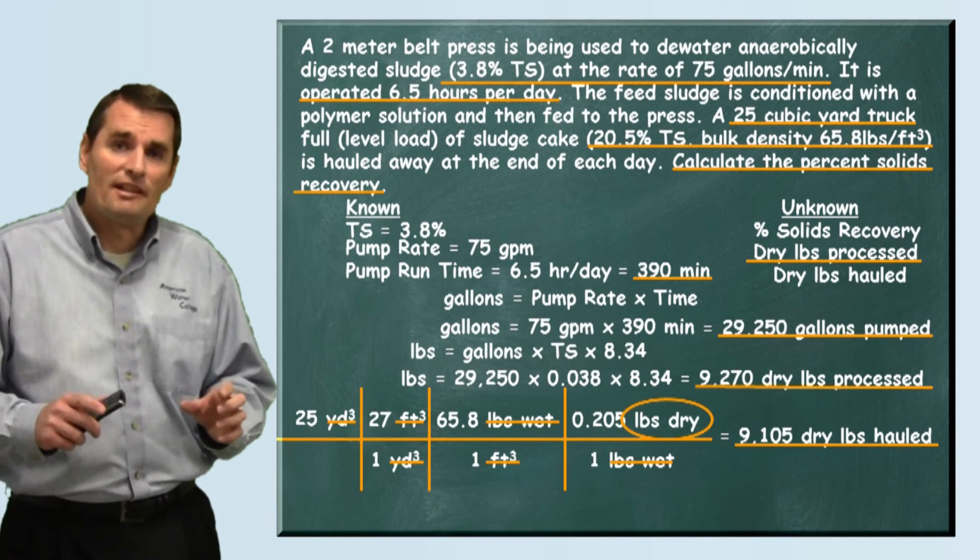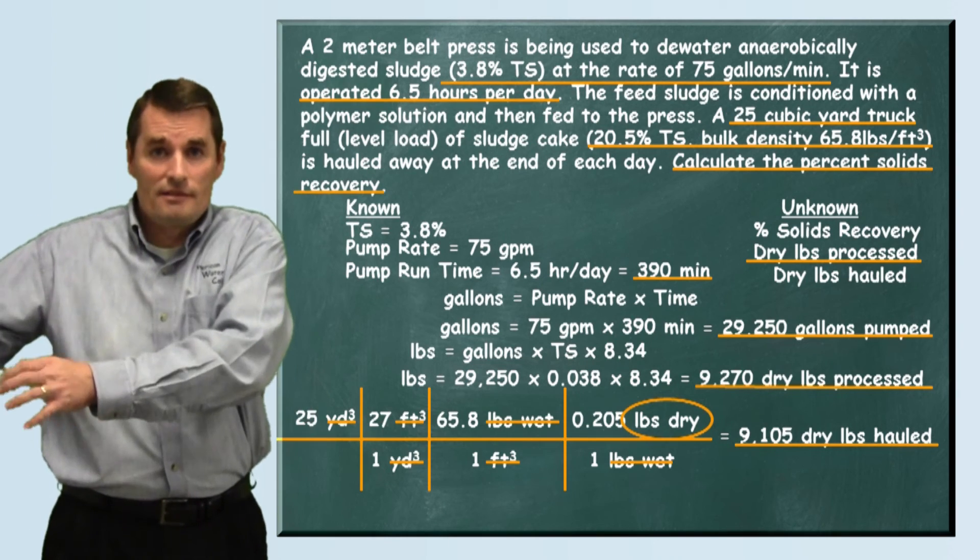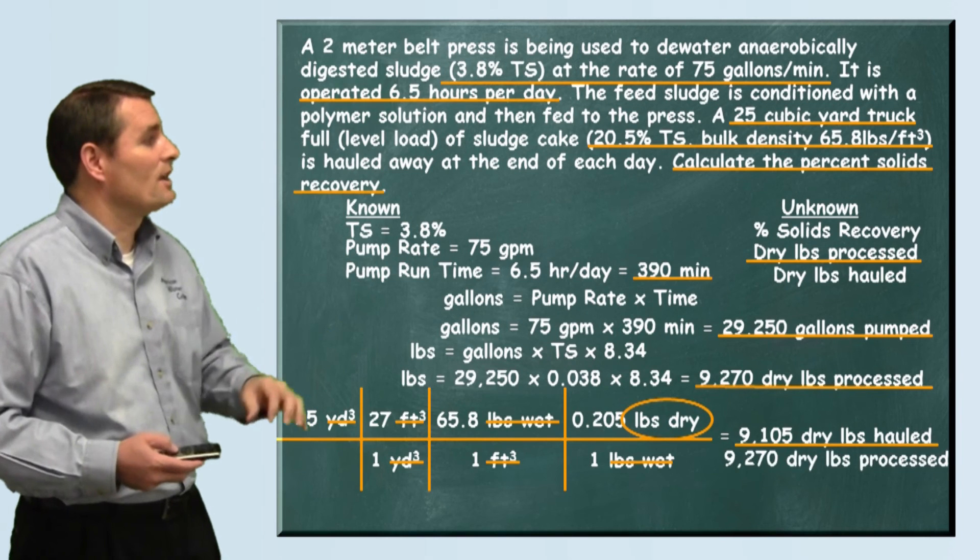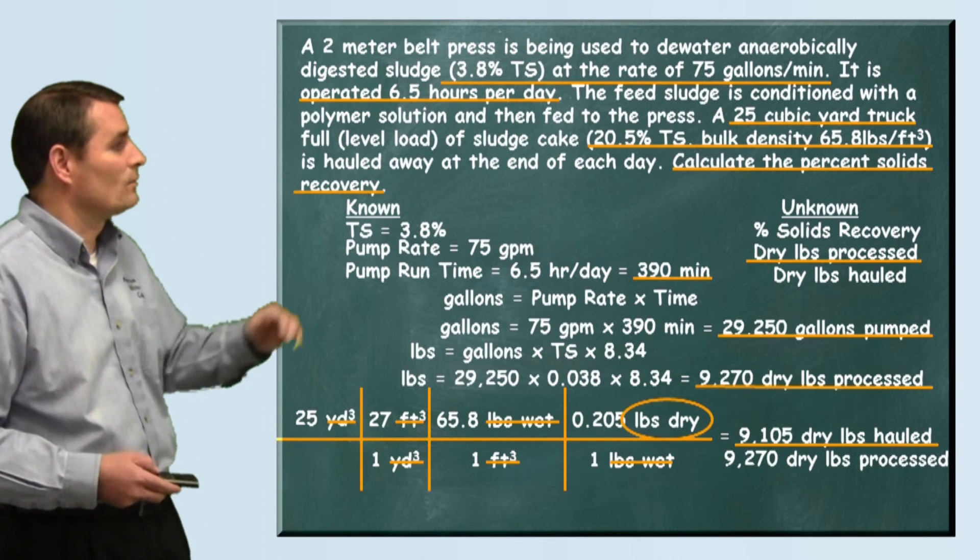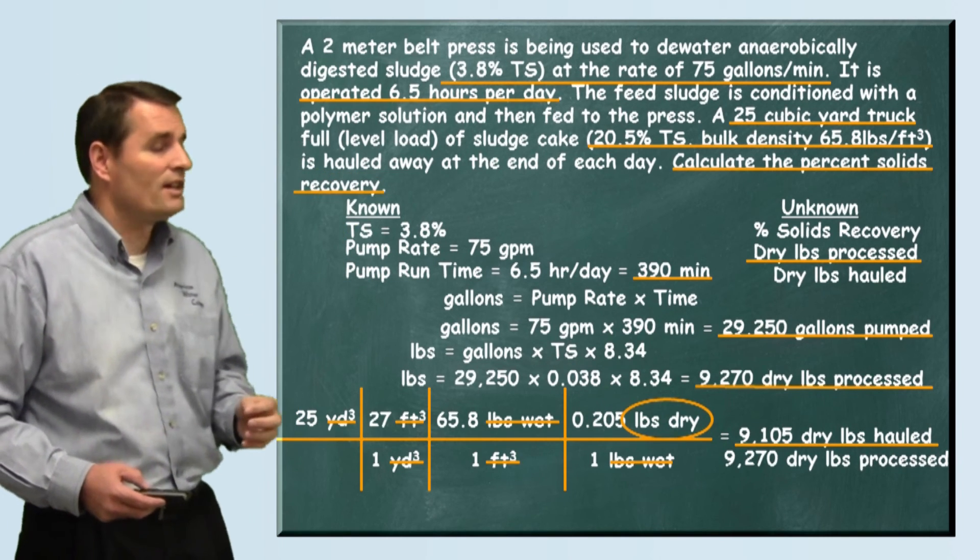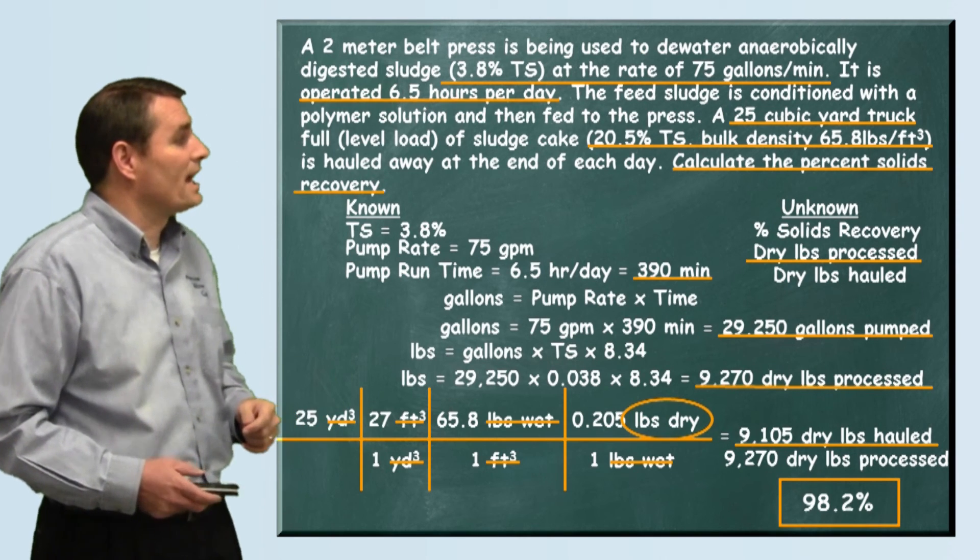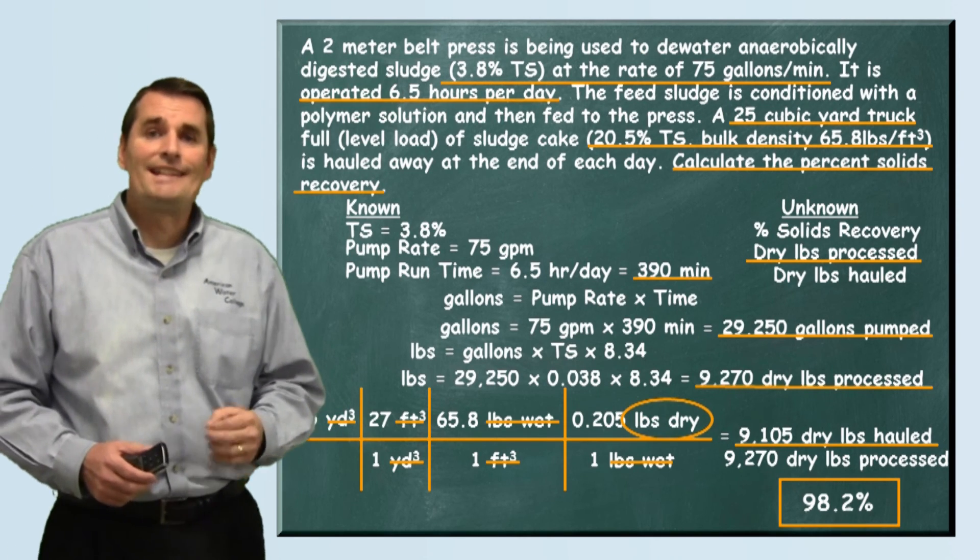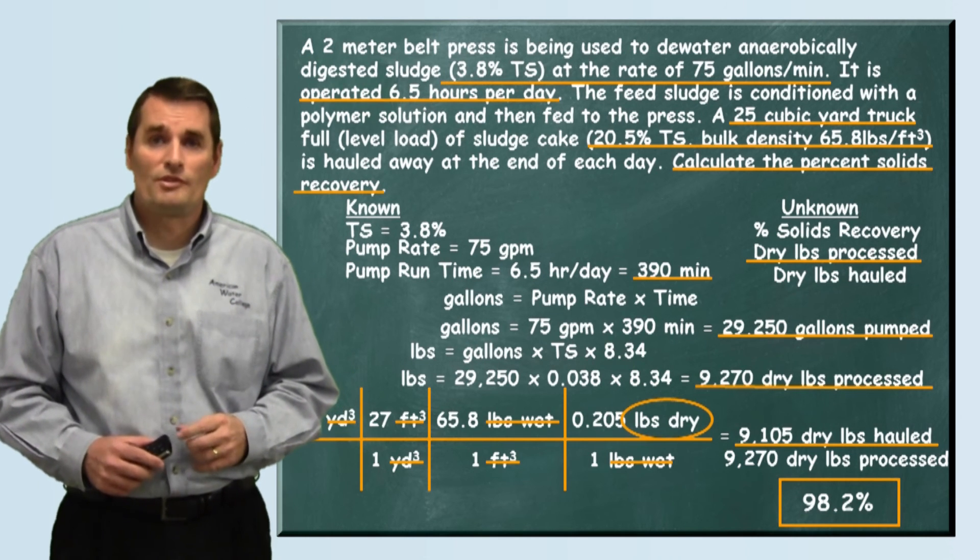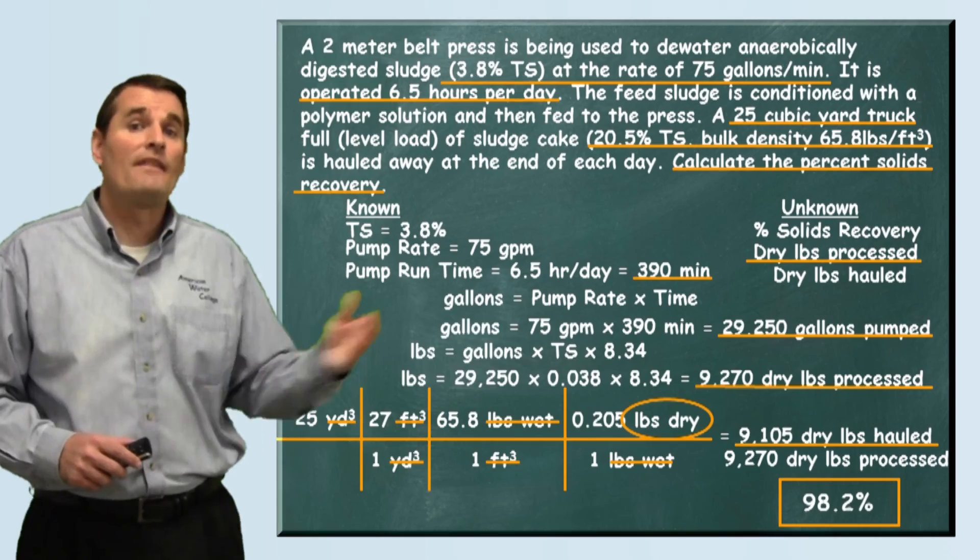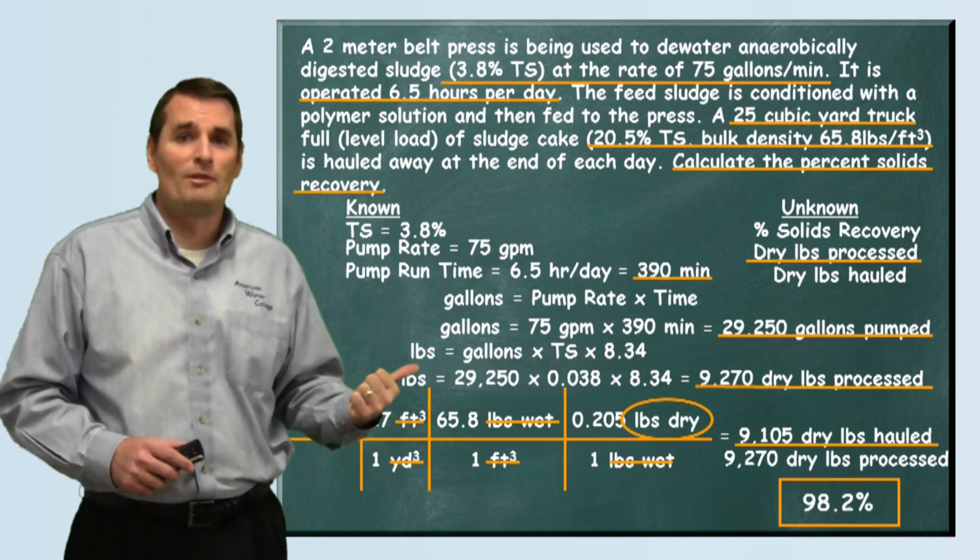Now we've calculated how much was sent to the press and how much was hauled away. We can use these two numbers and divide one by the other. We'll divide the 9,105 by our 9,270. When we do that we see that we recovered 98.2 percent of the total solids sent to the belt press. And that my friend is how this problem is solved.